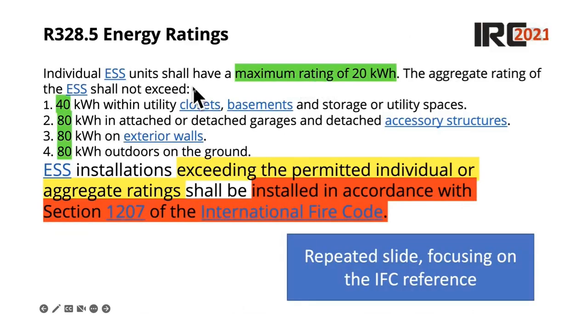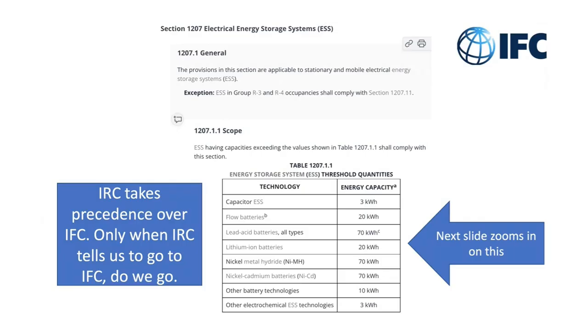And here is what we were just looking at, except for this one part at the end. So it says installations exceeding the permitted individual or aggregate ratings shall be permitted in accordance with the IFC, the International Fire Code. And so here is the International Fire Code. We can see here too, if we look at the lithium ion batteries, we have a similar table of 20 kilowatt hours here, but energy storage systems exceeding these values shall comply with this section. So actually it's saying if it's less than 20 kilowatt hours, you don't have to do the IFC.